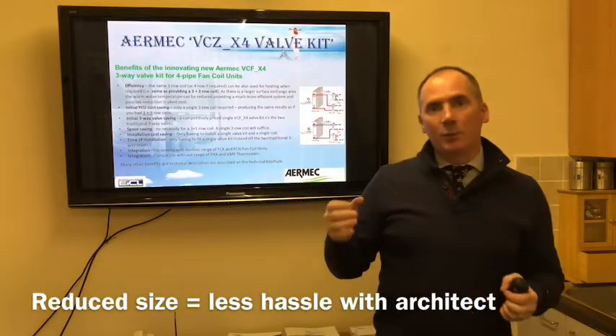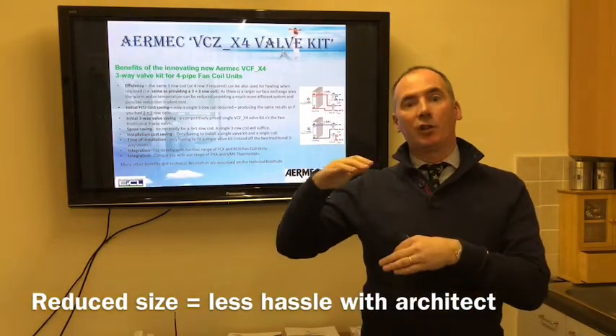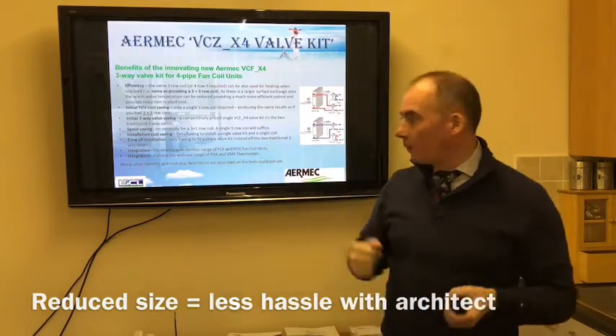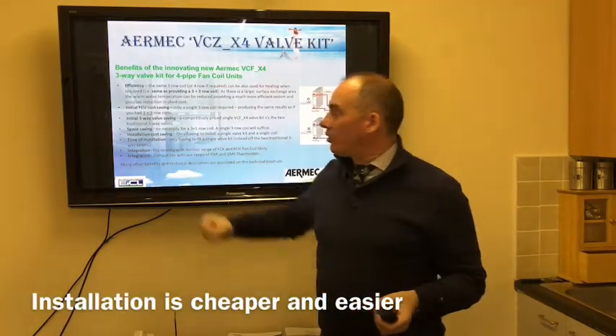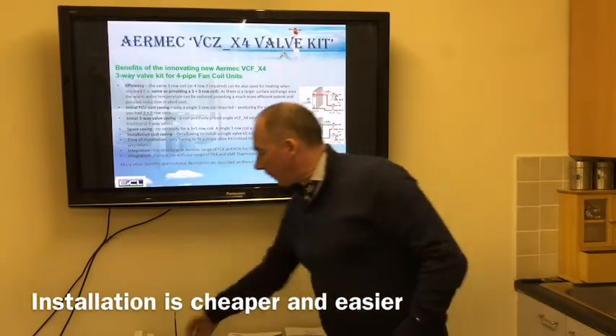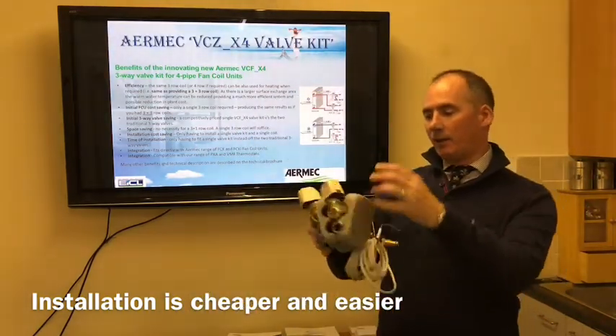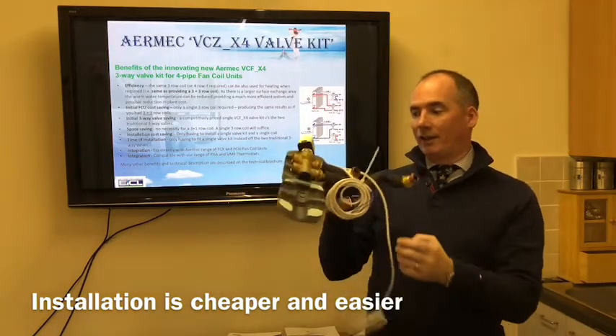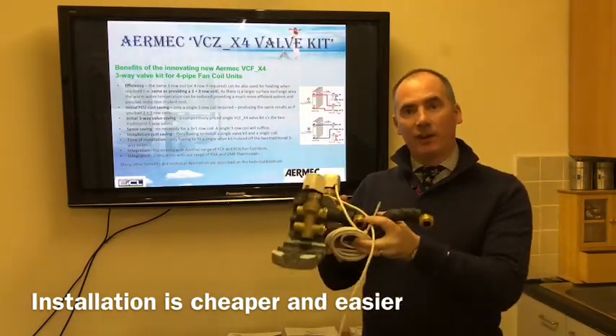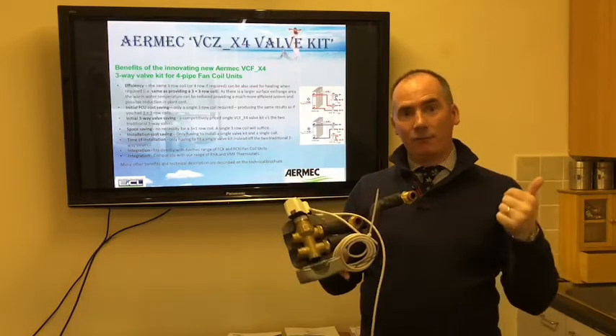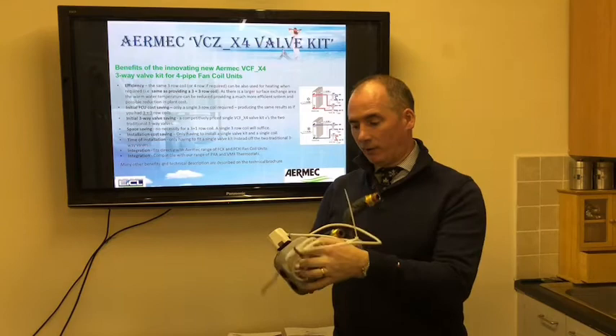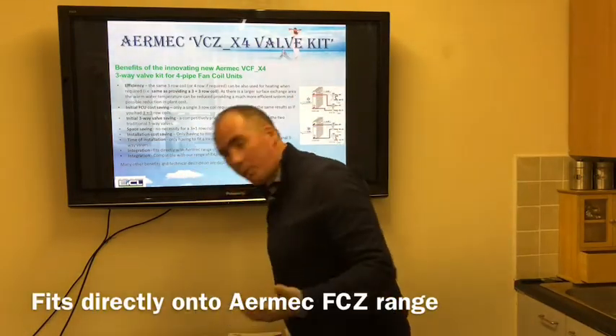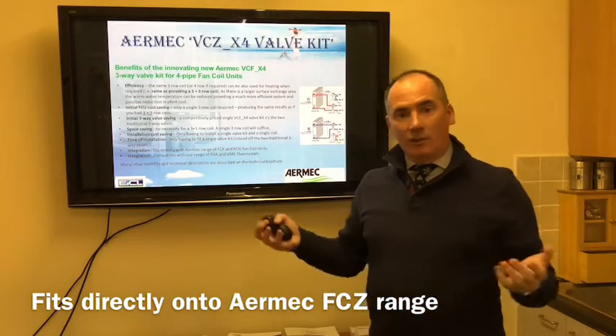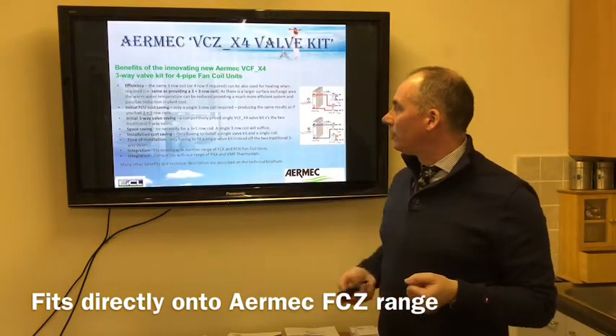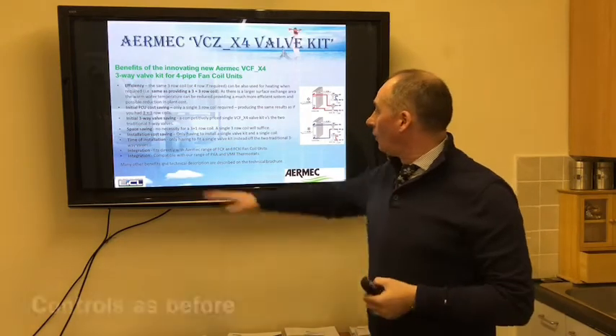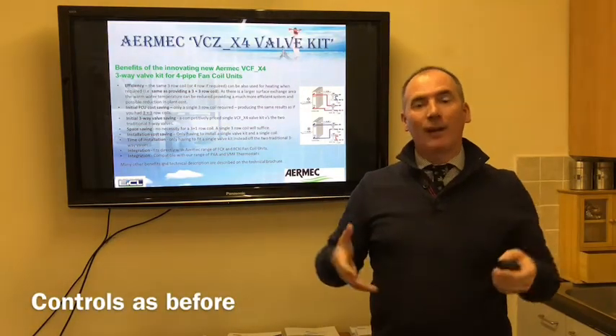Space, not always the case, but in certain models, the size of the unit will be physically smaller because it's only a 2-pipe, not a 4-pipe. Installation, it's much easier and cheaper to install. You don't have contractors trying to connect your valves in and do all your pipe work. Like I said, this comes as a kit, ready-made. It'll fit directly onto the FCZ range of fan coil units from Aermec. So nice, neat and easy to install, and consequently cheap to install. Time of installation is obviously quicker because of it, and integration, I mentioned, it's compatible with the Aermec range. Controls are pretty much the exact same as you would control a fan coil unit previously.